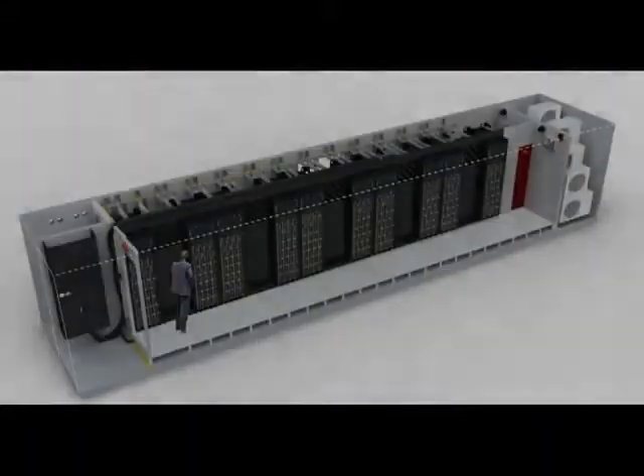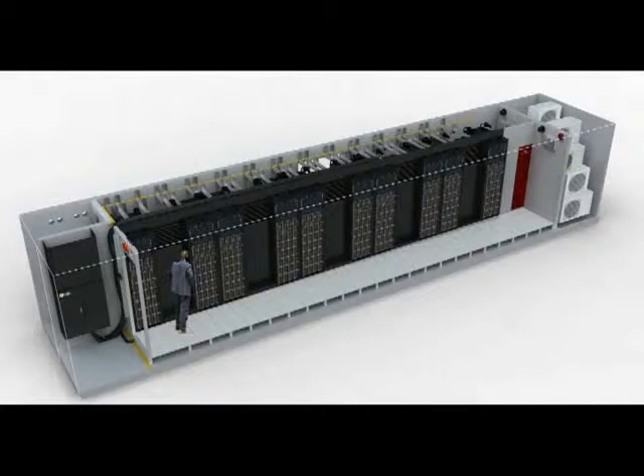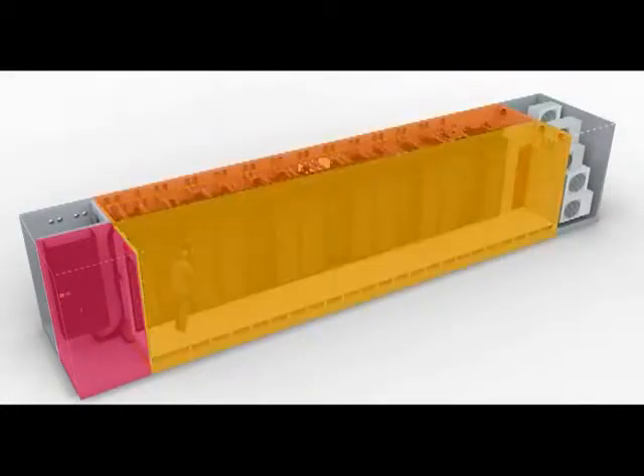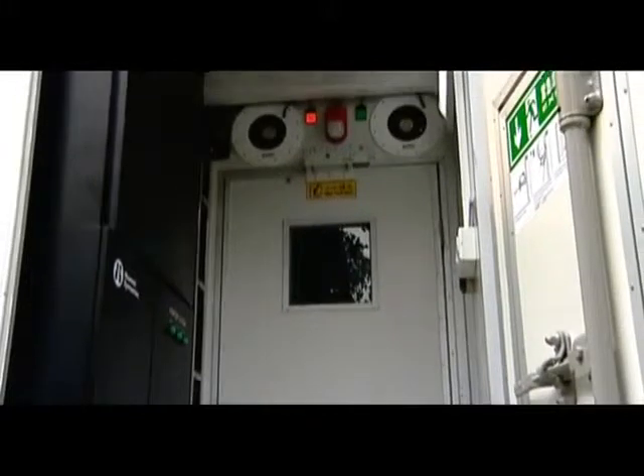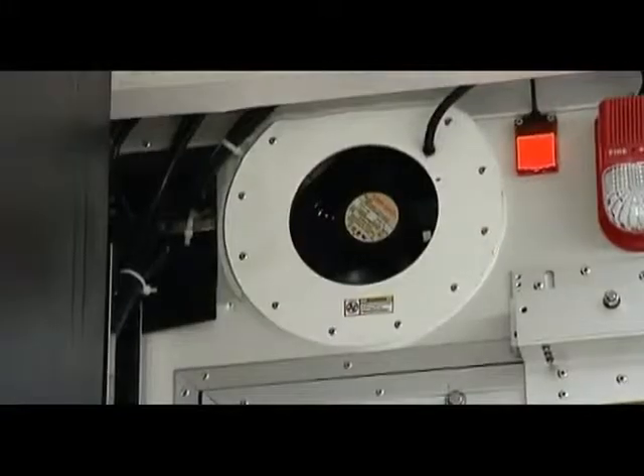The container data center is divided into three main sectors: the power supply area, the IT area, and the air conditioning condenser fan area. The power distributor panel and the lightning protection system control cabinet are in the power supply area, which is designed to be compliant with Class 3 lightning-proof standards.